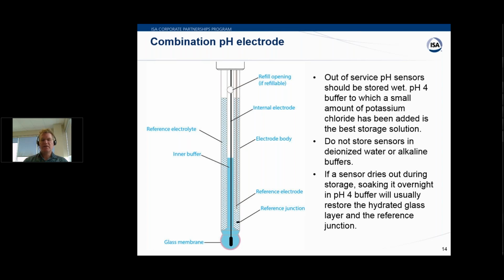But generally, like any of our instruments or equipment, we always have to maintain it. So our pH electrodes, when we're not using them, we generally need to store them wet, right? We're maintaining that gel layer. And so typically what we do is we store it in a pH 4 buffer solution, and do not put it in deionized water or alkaline buffers. So obviously deionized water means that there are no ions, so all the hydrogen that's inside, right, in that buffer, that would be high charge, so it would all want to leak out, right?